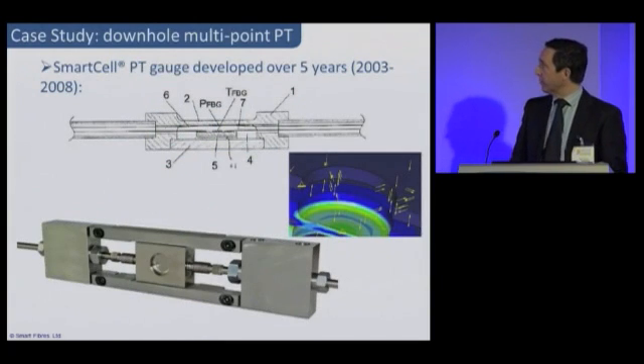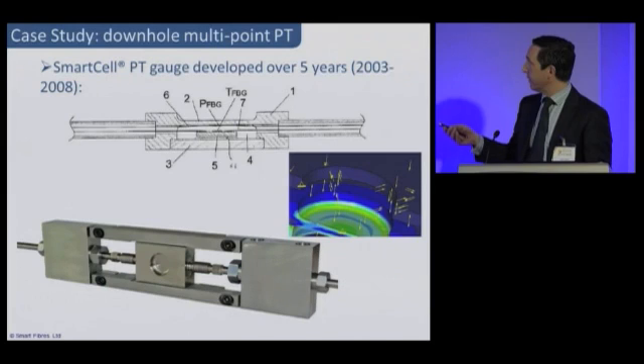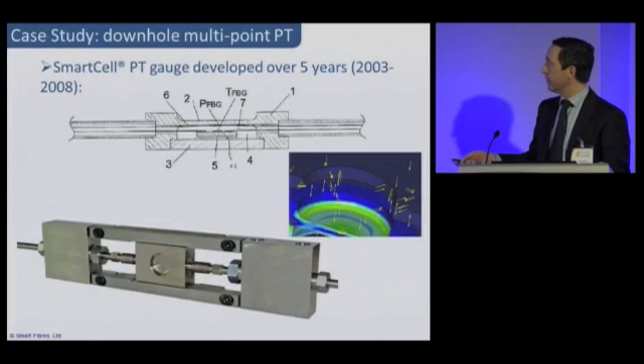So this is a product that we developed under this 5-year project with support and steer and some sponsoring from Shell. The gauge is a fibre Bragg grating pressure transducer. We have one fibre Bragg grating here on the back of a pressure-sensitive diaphragm. So when hydrostatic pressure is applied to the diaphragm here, the diaphragm deforms.